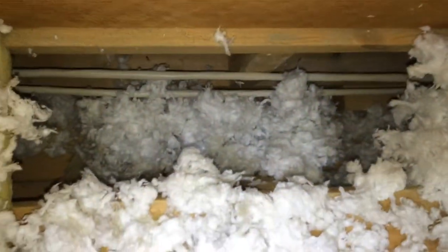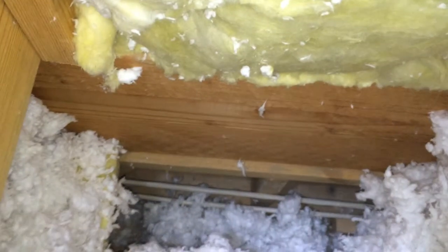It's better to cover this or switch to a different product like foam. When you start doing some hunting, take a look at this spot down here. There was a piece of fiberglass in here, and then down there's this big hole — it's nice and toasty in here right now. There's a bunch of air leakage down there. I can tell because all the fiberglass around here is a little bit gray, like that right there — gray fiberglass is a sign of air leakage.